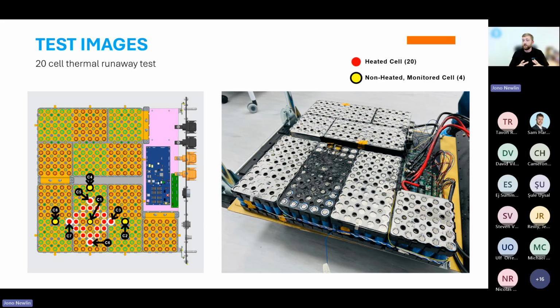So this was static liquid, emphasizing protection against thermal runaway risk, and it stayed localized to that area. I believe there was a row of propagation, but it's even more impressive that cells adjacent to those 20 may have triggered without causing a cascading event, because the liquid was able to absorb the heat. If we look at that single cell, C1, it's in the center of all of these.